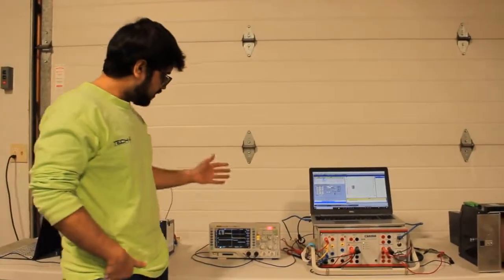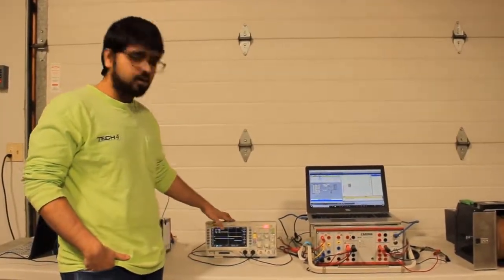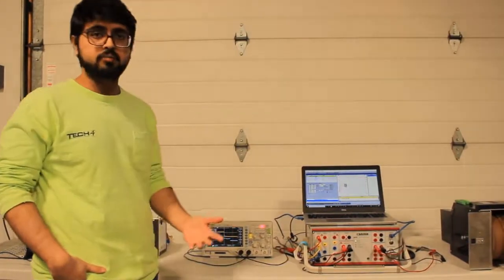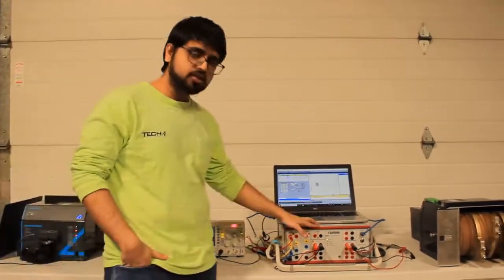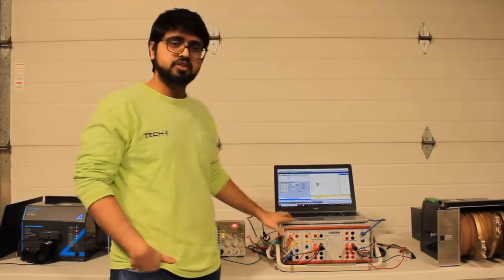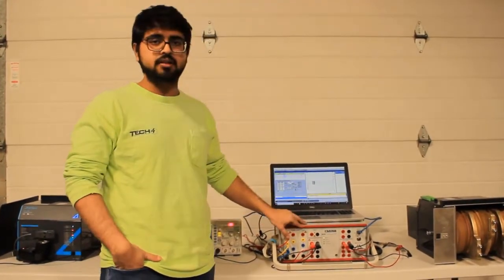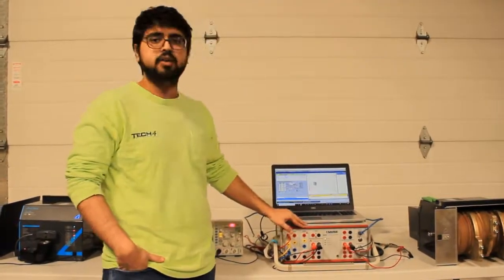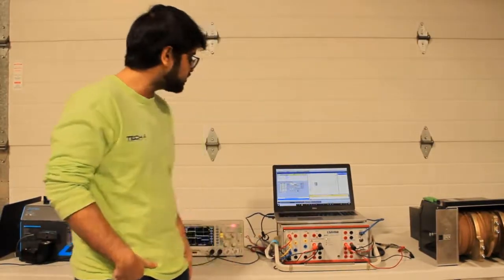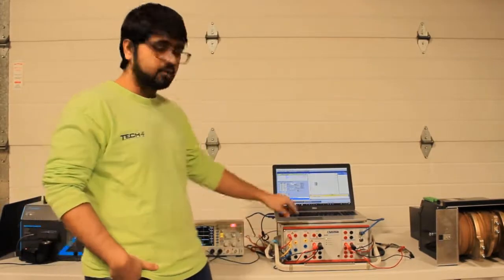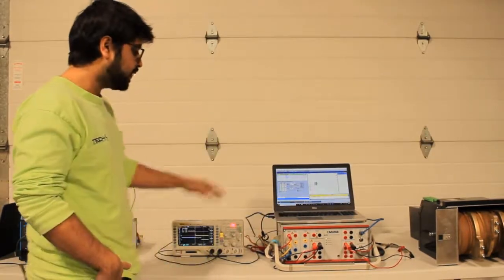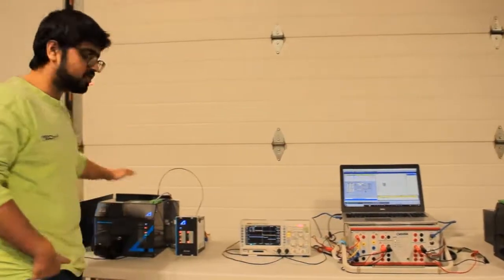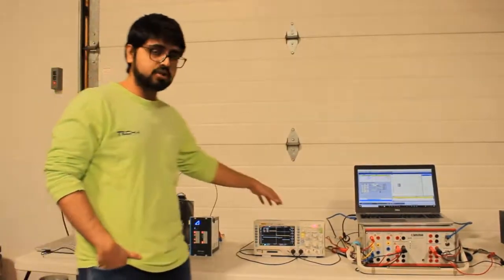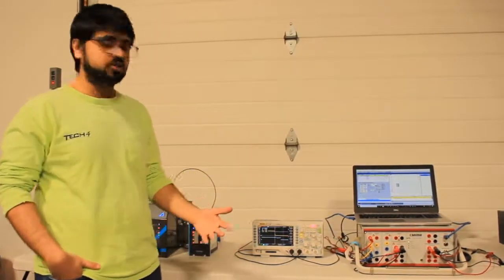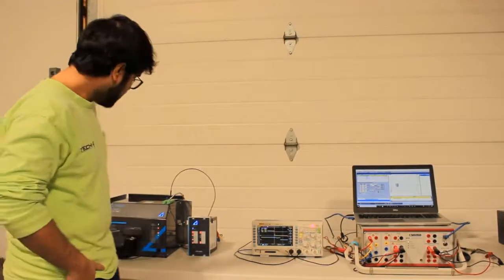So as we saw, we could measure the time on an oscilloscope and confirm that it was under 3 milliseconds. The tester, the Ponovo test kit, also measures the time, but it includes a latency time, and it might not be accurate and might not be under less than 5 milliseconds. In this case, it was close to 7 milliseconds, but that includes the latency time, and that's not the exact time the quencher takes to quench. That is why we've used an oscilloscope to verify that it quenches under 5 milliseconds.